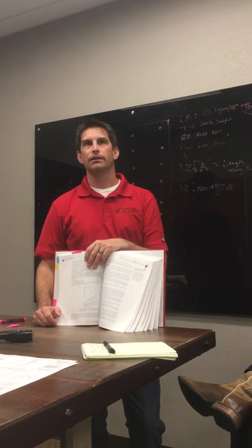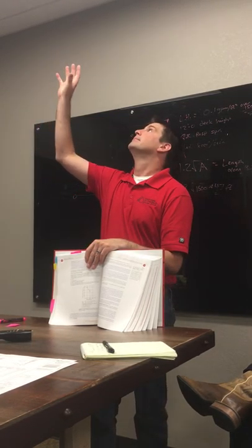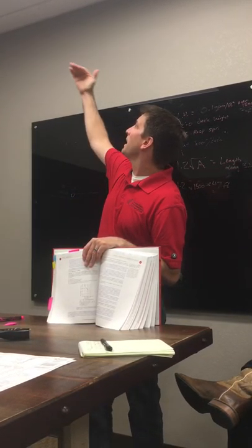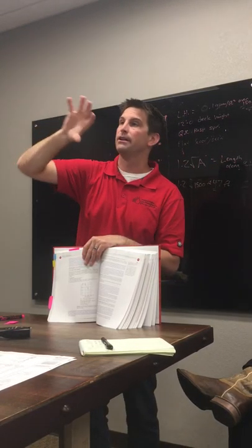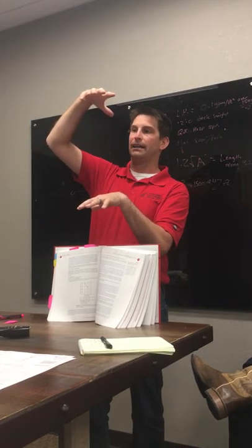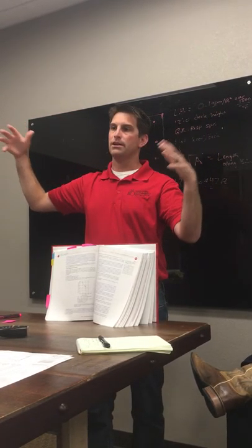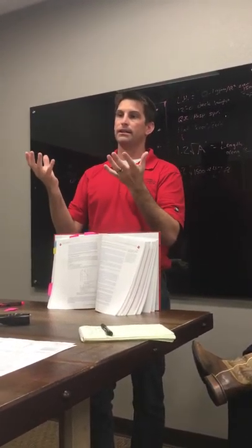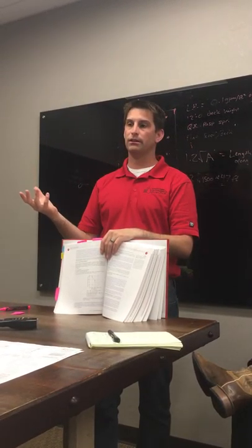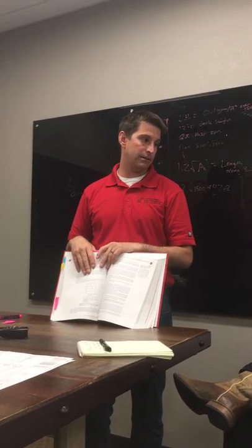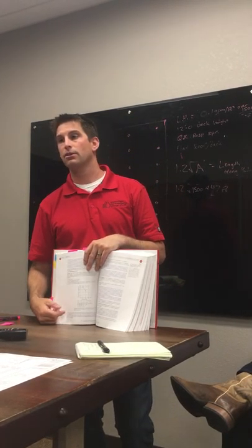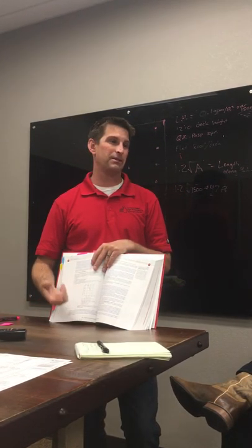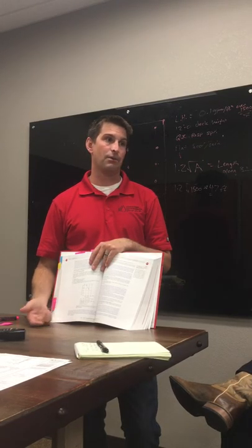But let's say that right here the ceiling came out, then it jumped up 3 feet and went across and dropped back down 3 feet, and you had kind of a skylight-looking pocket. You didn't have a sprinkler inside there, you just had the sprinklers down below. That ceiling pocket now doesn't have a sprinkler in it. It's saying if you design the system that way, you can't do quick response. So a lot of times, so that I can take quick response, I'll put a head in the ceiling pocket. It's not worth it otherwise.